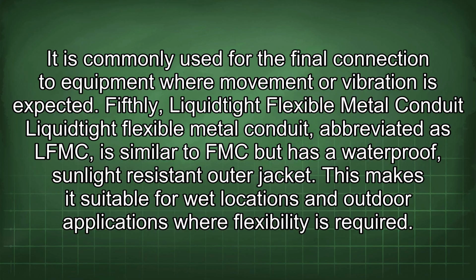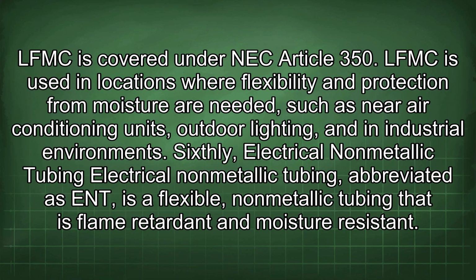Fifthly, liquid-tight flexible metal conduit. Liquid-tight flexible metal conduit, abbreviated as LFMC, is similar to FMC but has a waterproof, sunlight-resistant outer jacket. This makes it suitable for wet locations and outdoor applications where flexibility is required. LFMC is covered under NEC Article 350. LFMC is used in locations where flexibility and protection from moisture are needed, such as near air conditioning units, outdoor lighting, and in industrial environments.